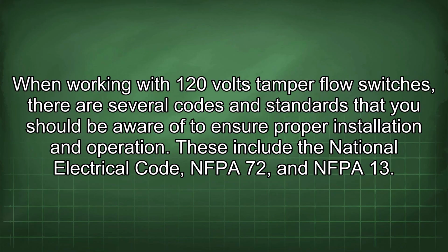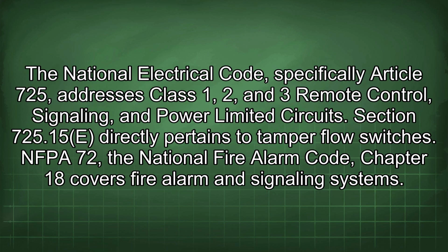When working with 120 volts Tamper flow switches, there are several codes and standards that you should be aware of to ensure proper installation and operation. These include the National Electrical Code, NFPA 72 and NFPA 13. The National Electrical Code, specifically Article 725, addresses Class 1, 2, and 3 remote control, signaling, and power-limited circuits.